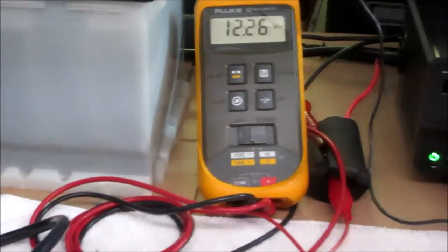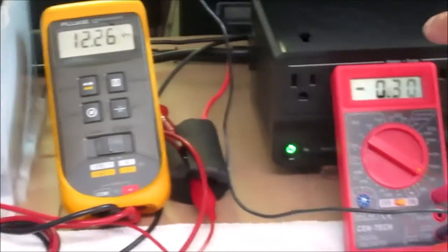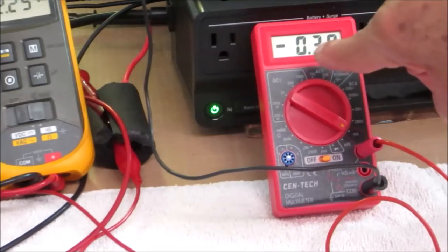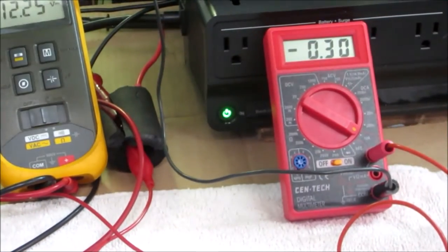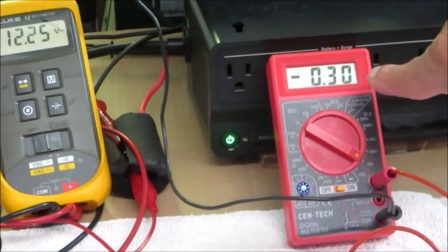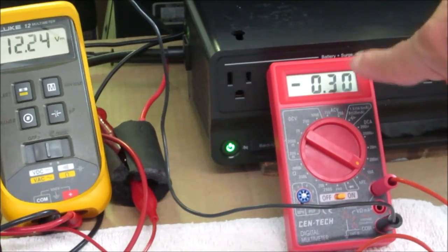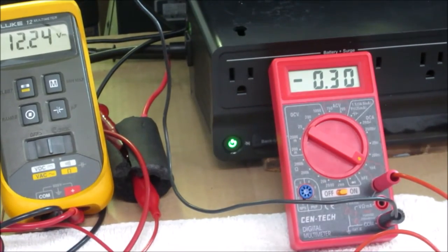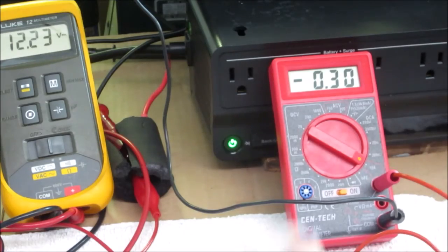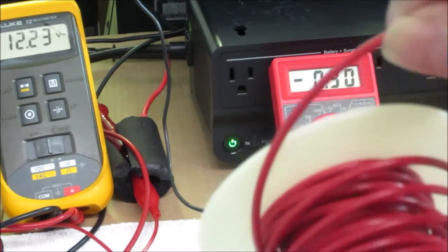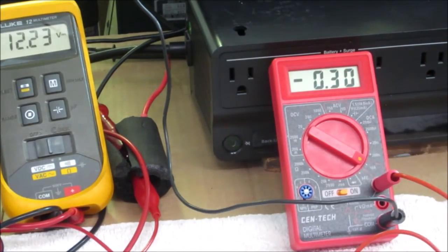In the manual it tells you how to turn off all alarms. For the moment, we were putting 0.6 of an amp into the battery and drawing 0.3 of an amp out of the battery. That tells us how thick the wire has to be, and this 14 gauge automotive wire is just fine, whether I had thought about this or not.